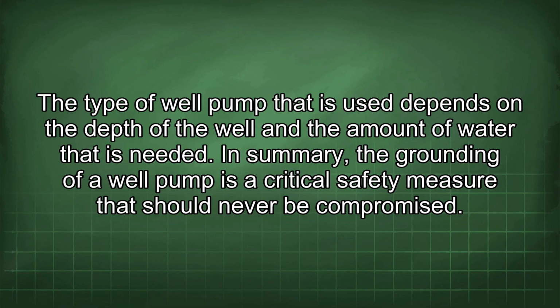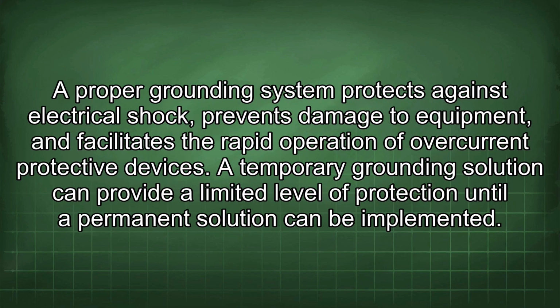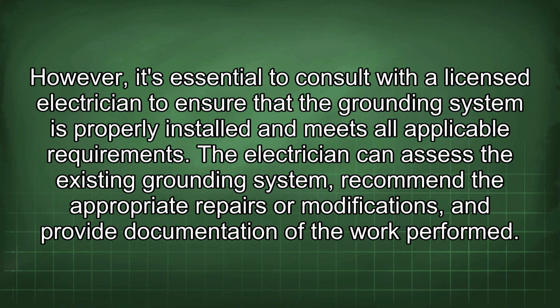In summary, the grounding of a well pump is a critical safety measure that should never be compromised. A proper grounding system protects against electrical shock, prevents damage to equipment, and facilitates the rapid operation of overcurrent protective devices. A temporary grounding solution can provide a limited level of protection until a permanent solution can be implemented. However, it's essential to consult with a licensed electrician to ensure that the grounding system is properly installed and meets all applicable requirements. The electrician can assess the existing grounding system, recommend the appropriate repairs or modifications, and provide documentation of the work performed.